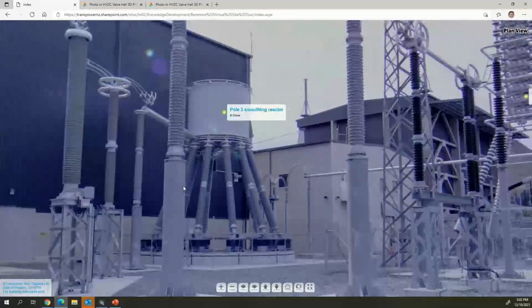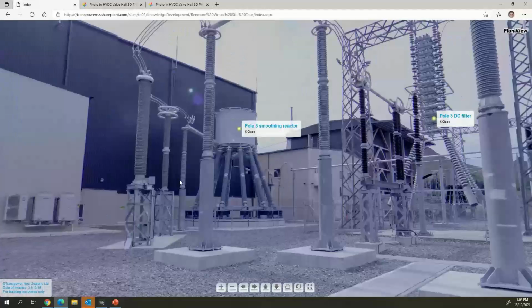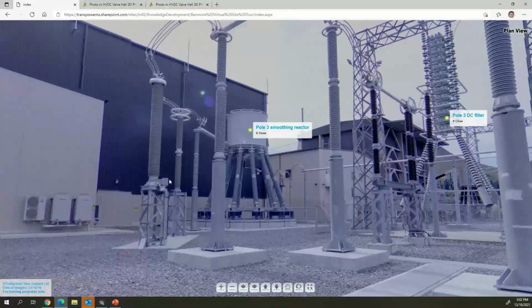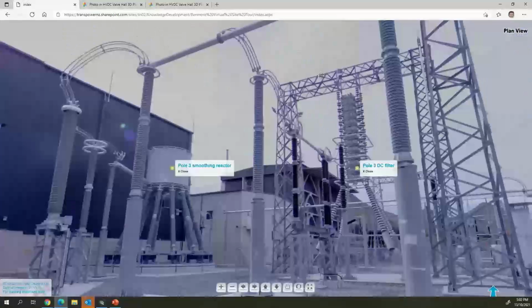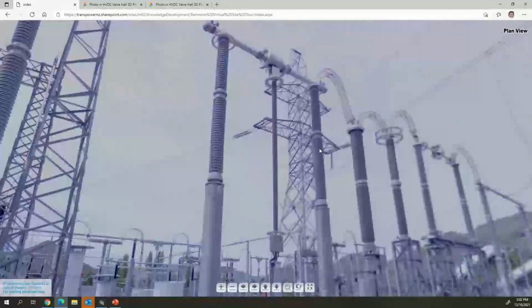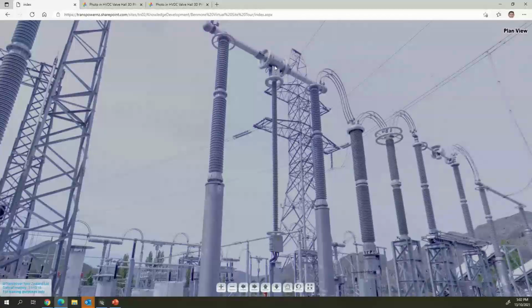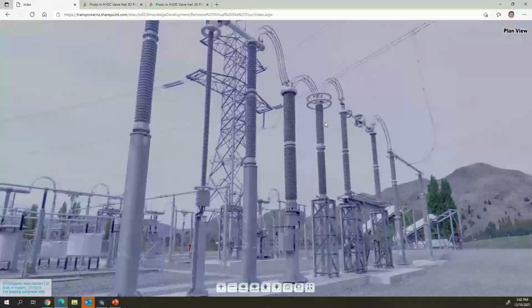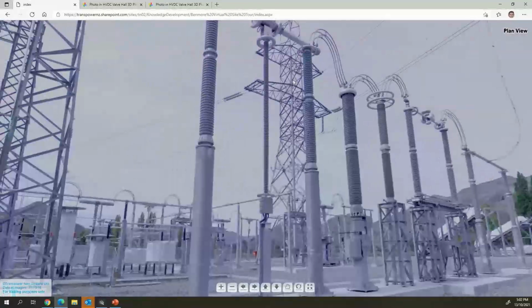We see some special HVDC equipment that you don't see very often. There's a voltage divider here, so you can't just use a normal VT for HVDC. You've got to use voltage dividers. That's to measure the voltage, and to measure the current, we use these things called current shunts. This is on pole 3. We use current shunts. It's basically just like a resistance in series, and you just measure the voltage across it. So pretty simple, but it works pretty good. You can see the DC line in the background there with the 2 poles. We'll cruise over to pole 2.